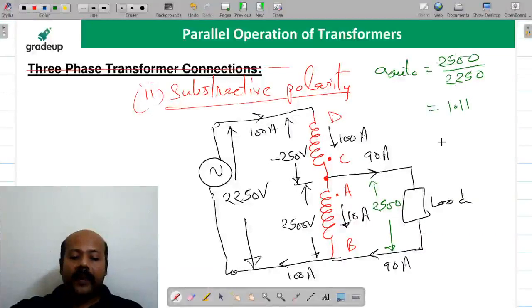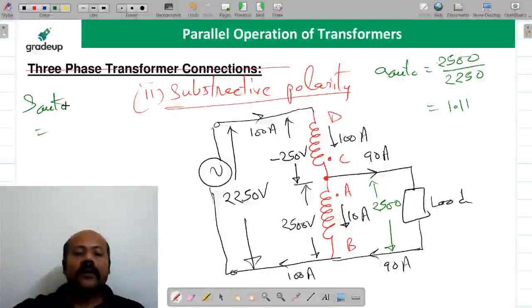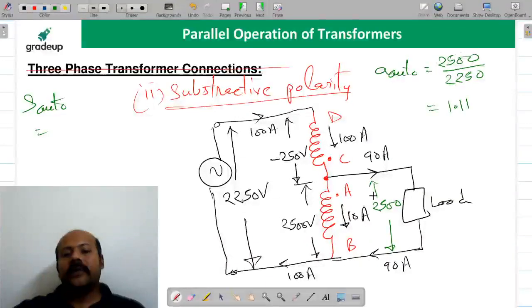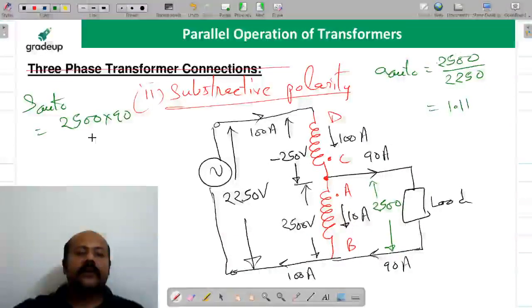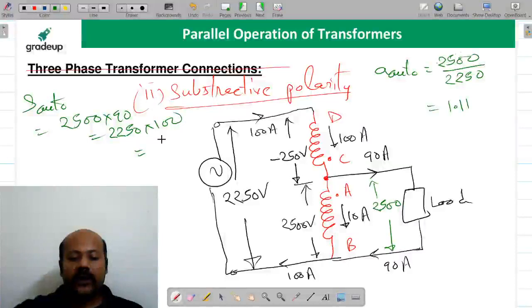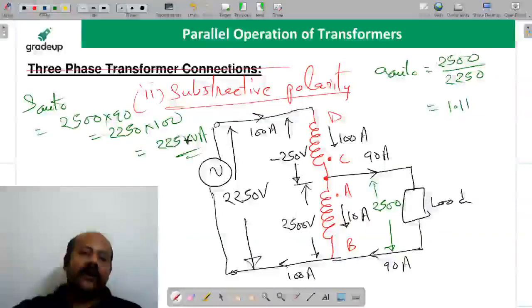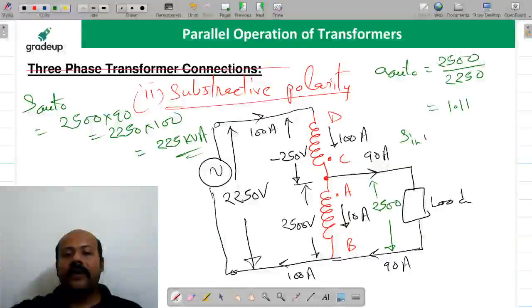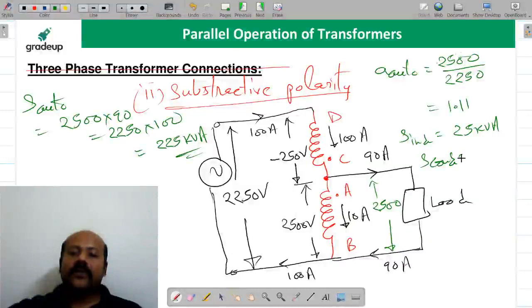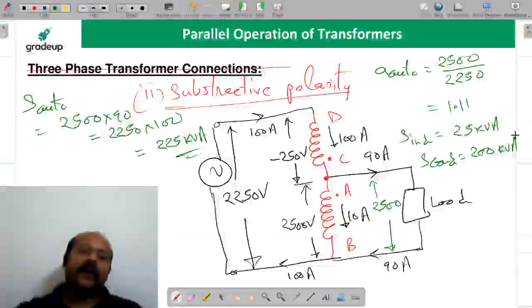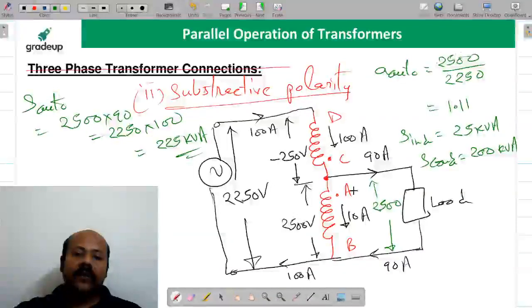Is it clear? Now, if you want to find the kVA rating of the autotransformer, you can find it from either the low voltage side or the high voltage side, it will be the same. From the low voltage side, it is 2250 multiplied by 100, giving 225 kVA. Directly you can say the inductively transformed kVA is 25 kVA, and the conductively transformed kVA is 200 kVA. Is it clear to all of you?